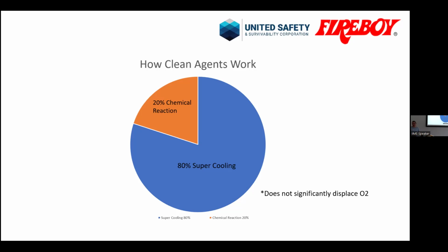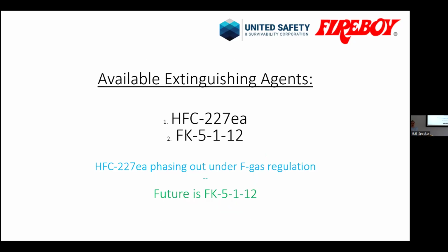So that's the common misconception between the CO2 halon and these clean agents. With the right concentration, it puts out the fire quickly. The two most common agents we still use are HFC 227, brand name FM200, and FK 5-1-12, brand name Novec 1230. As you probably are aware, or should be aware, HFC is a controlled substance under F-gas.